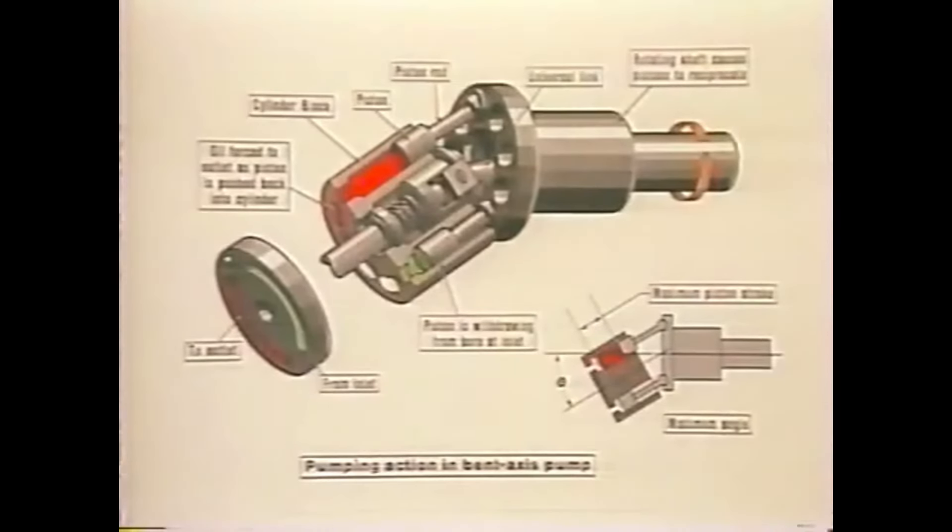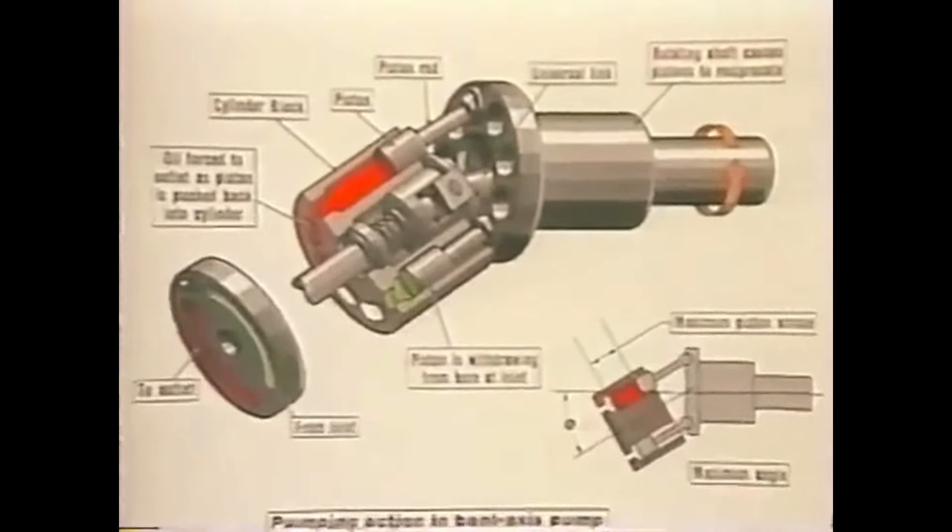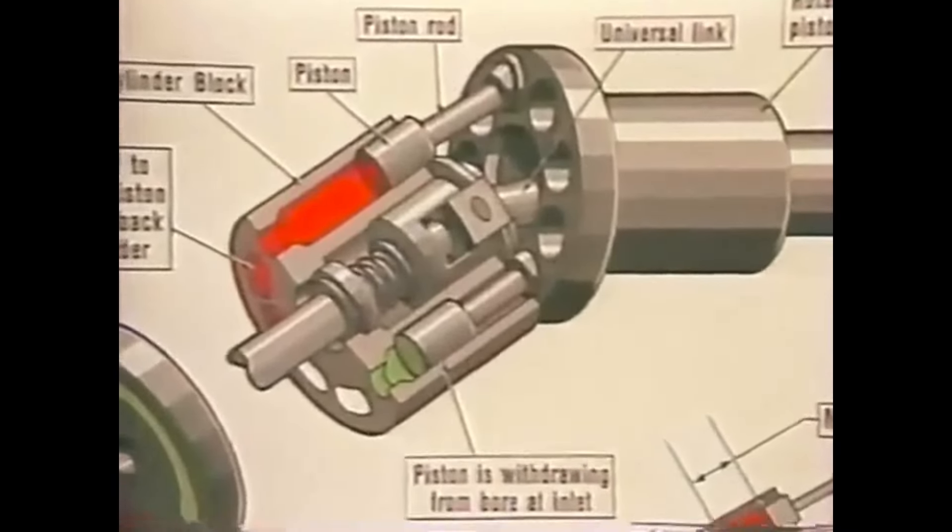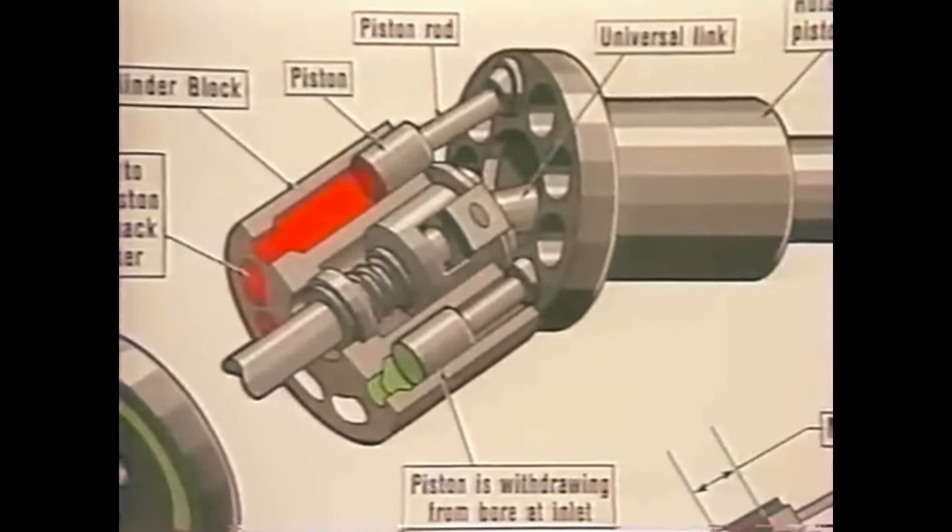In axial pumps, the pistons are parallel to each other and to the cylinder block axis. They may be either bent axis or inline units. The cylinder block in a bent axis pump rotates at an angle to the drive shaft. The pistons are fastened to the drive shaft flange by ball joints and are forced in and out of their bores as the distance between the cylinder block and drive shaft flange changes.